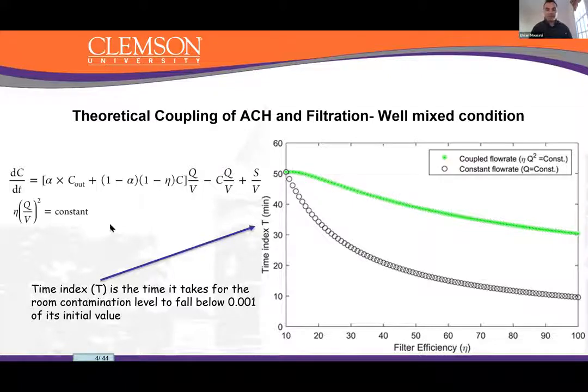The reason I'm showing you this is that often, and this came up as a question from the panel, when you have a fixed fan in your HVAC system and you change the efficiency of the filter in front of it, improving that efficiency creates more resistance, meaning the rate of air going through the filter can go down. These are coupled problems—you increase one, but the other is affected by that decision.